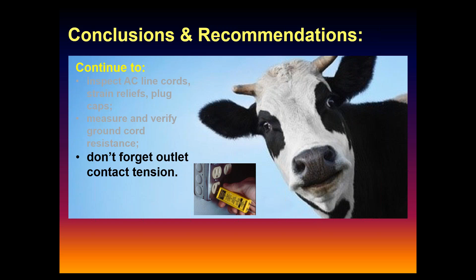The ground is also very helpful in controlling and minimizing some of the electromagnetic radiation that's being generated inside the device itself. So there are some other benefits from having an intact ground. That makes sense. Just be aware that there is also ohmic resistance between that ground pin and the receptacle. If that gets too sloppy, typically about 4 to 8 ounces of retention force or so, you're going to have a lot of resistance in there, reducing the effectiveness of the ground.